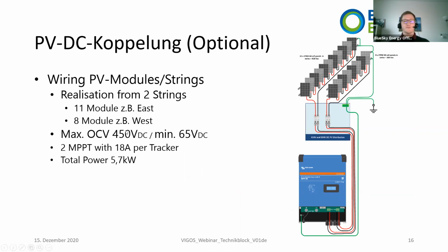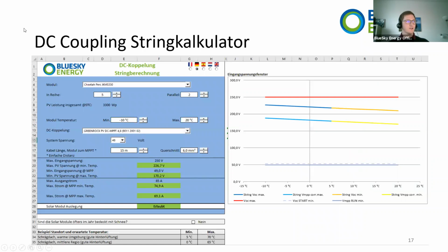That means most of the time you can place a maximum of 10 panels in series, depending on your panel choice. If you already have your defined panel, you can use our string calculator tool. It's an Excel tool where you can fill in the data of your PV panel model, and the string calculator then tells you if your planned configuration is usable or not. You can fill in how many modules you have in series and how many you have in parallel.